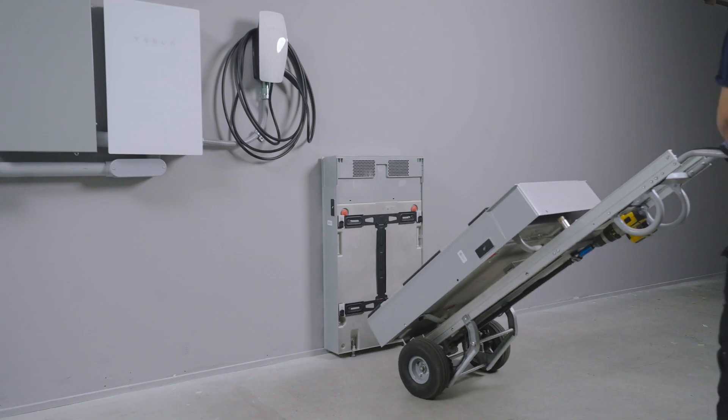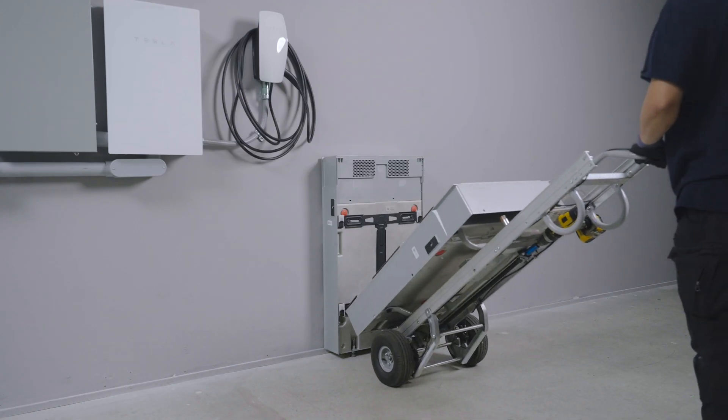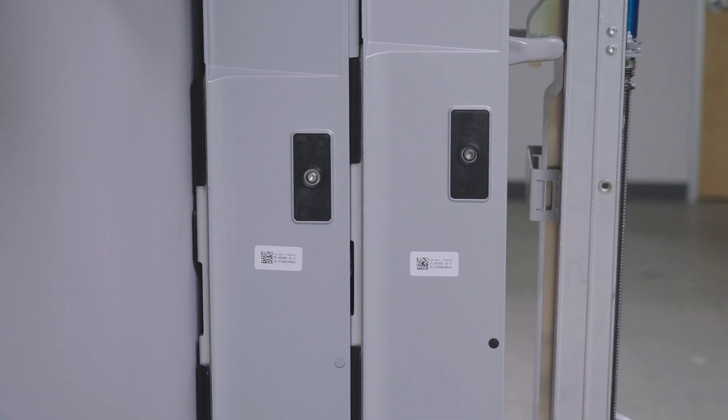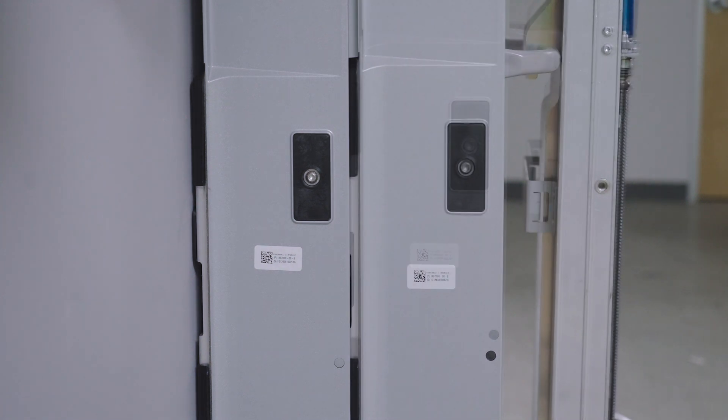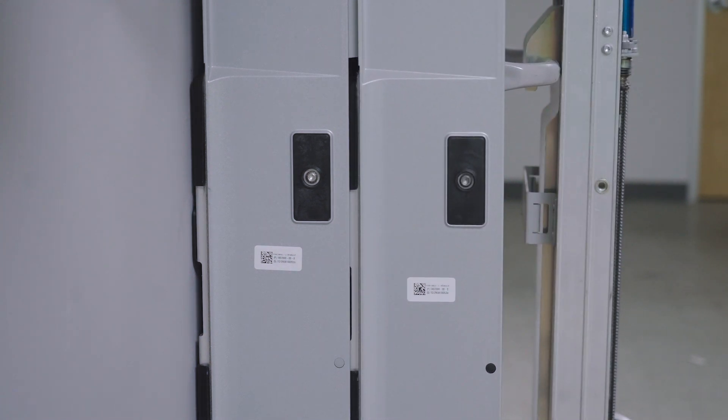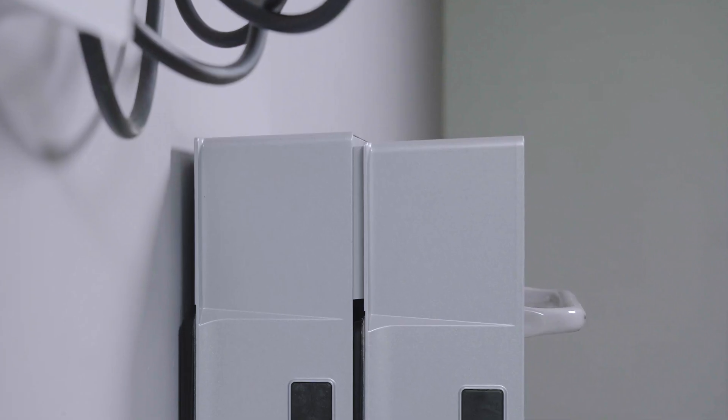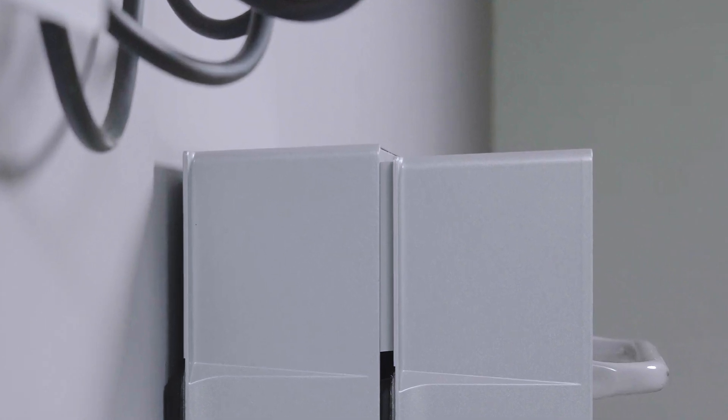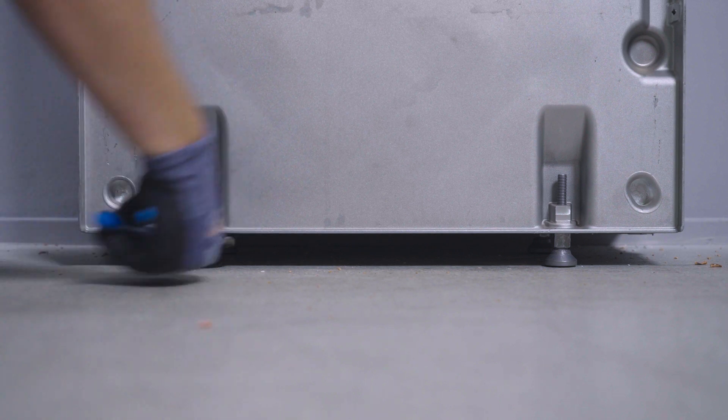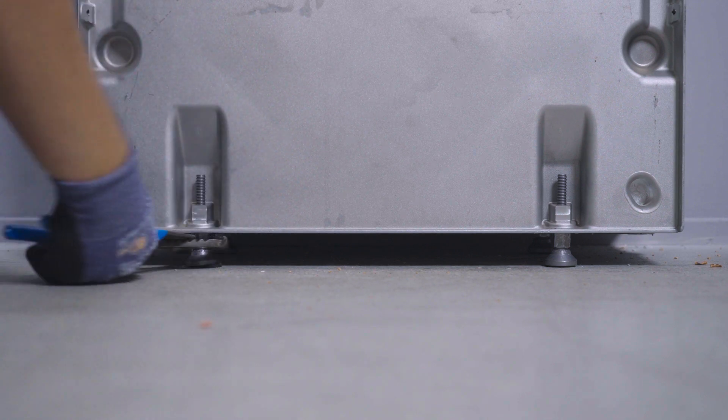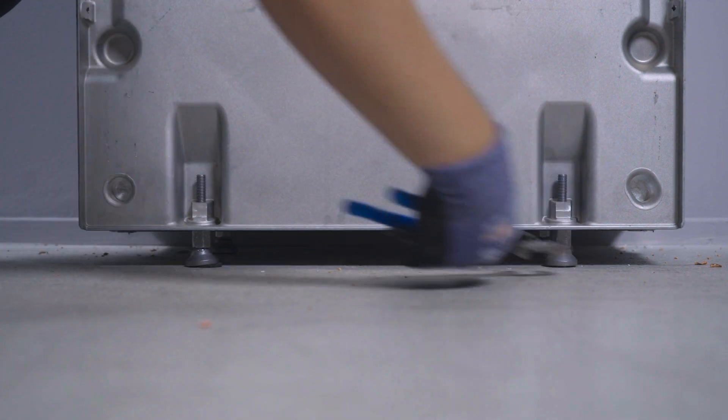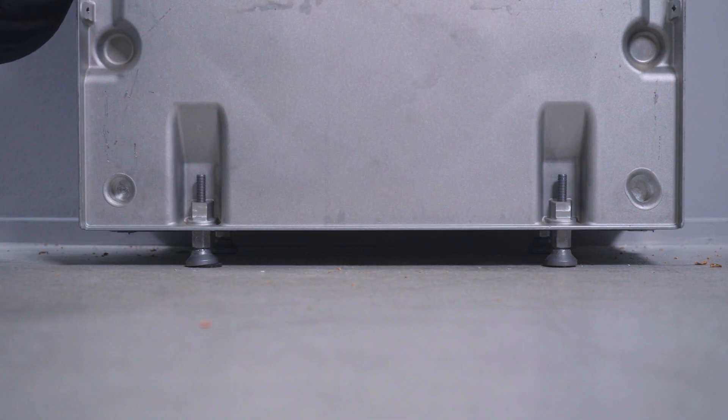Gently lower the next unit in the stack onto this bracket, either Powerwall 3 or another Powerwall expansion unit. The front unit will sit slightly lower than the unit it is mounted to. Adjust the leveling feet to align the mounting level of each unit.